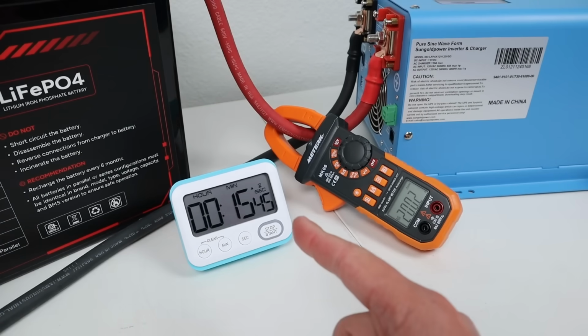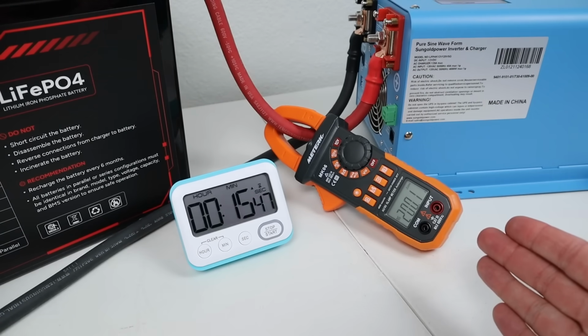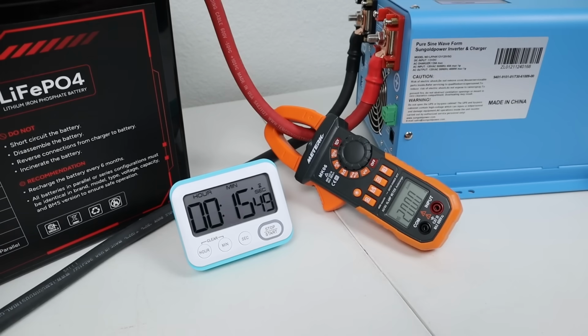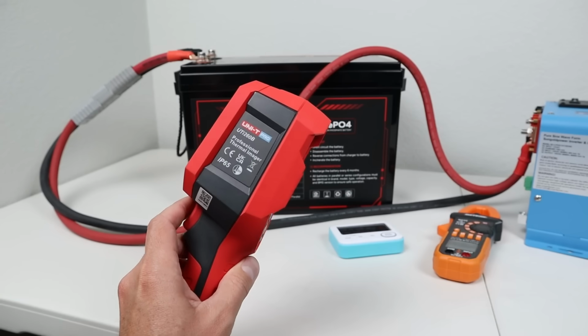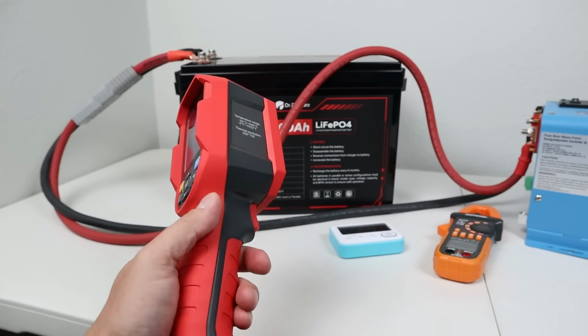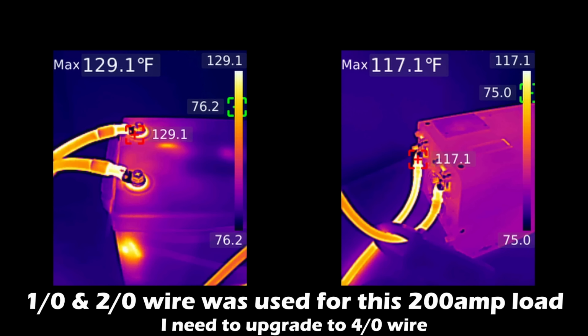Okay, so it's been going for a little over 15 minutes, and it's still running the 200 amp load, so yes, it can handle 200 amps maximum output without shutting down. Now after the test had finished, I did use my thermal camera to measure the battery terminals. I like to do this to see if the conductors on the inside of the battery are undersized or not. Now I measured 130 degrees, or a little bit under that, and my inverter measured 117 degrees. So these temperatures are pretty close together. I'm guessing they are using decent conductors on the inside of the battery. We'll find that out as we do a teardown later in the video.